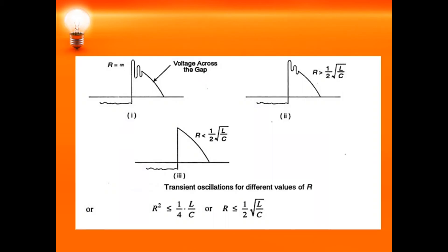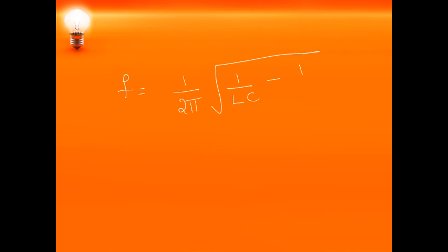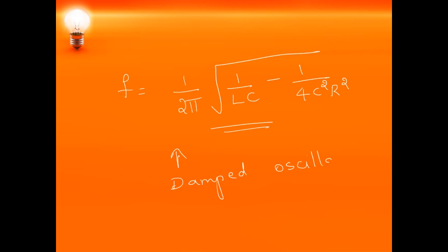Observing transient oscillations for different values of R: when R is infinity or greater than the critical value, transients are present; when R is less than or equal to the critical value, there are no transient oscillations. The frequency of the damped oscillation is: f = (1/2π)·√(1/(LC) − 1/(4C²R²)). By connecting a resistance of the appropriate value, we can reduce the restriking voltage and the RRRV.